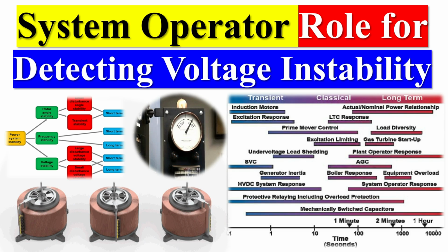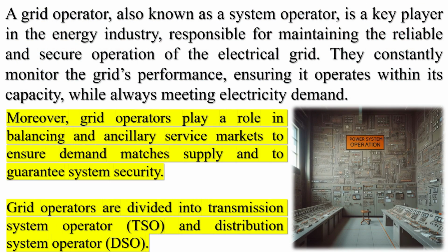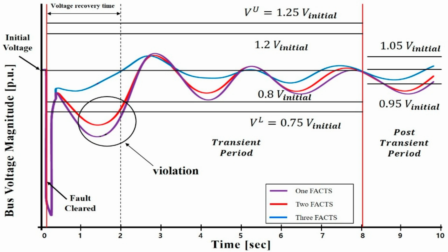This subject is quite difficult and complex to summarize. I will try to share as much as possible. Voltage stability refers to the ability of a power system to maintain steady voltages at all buses in the system after being subjected to a disturbance from a given initial operating condition. Principal causes of voltage instability are heavy load system operation conditions, long distances between generation and load, low source voltages, and insufficient reactive power compensation.